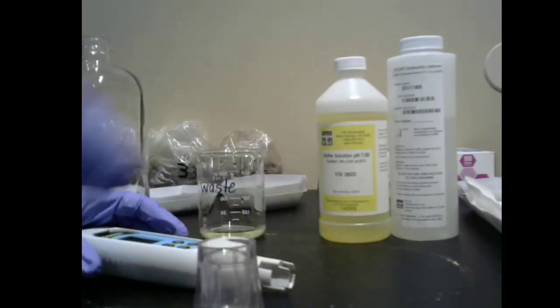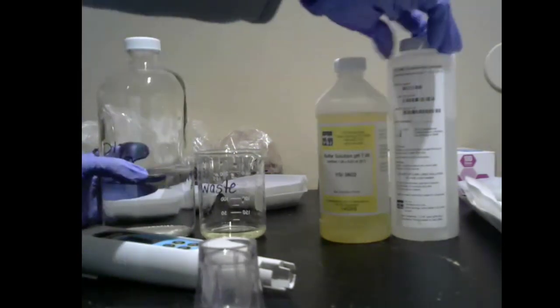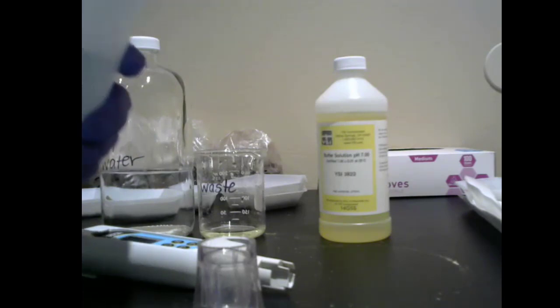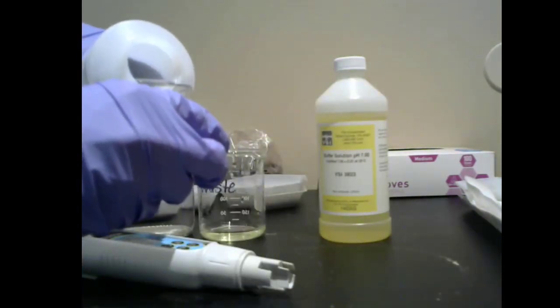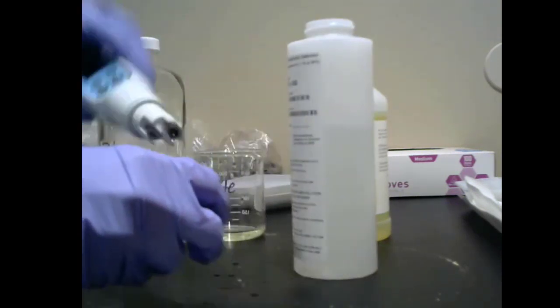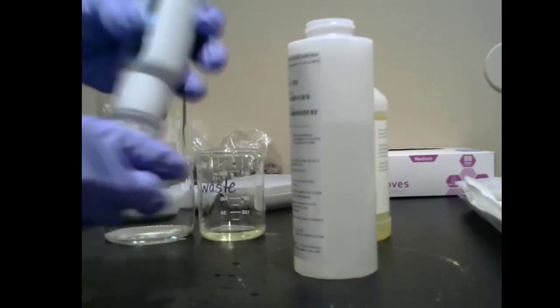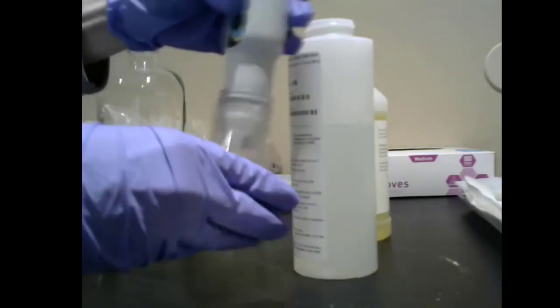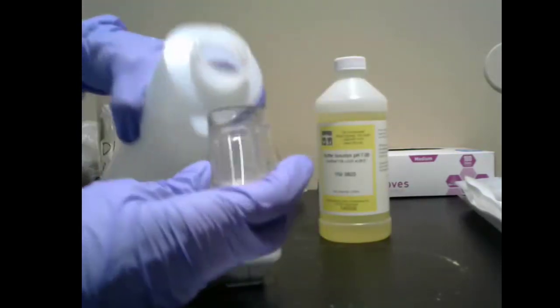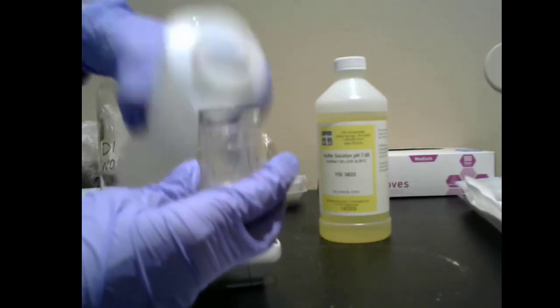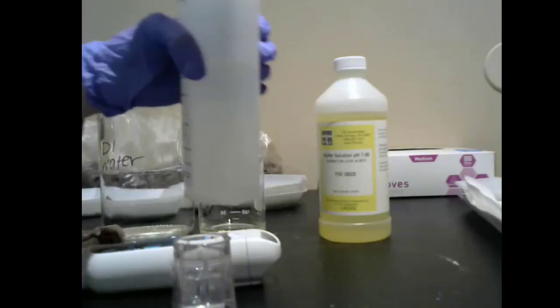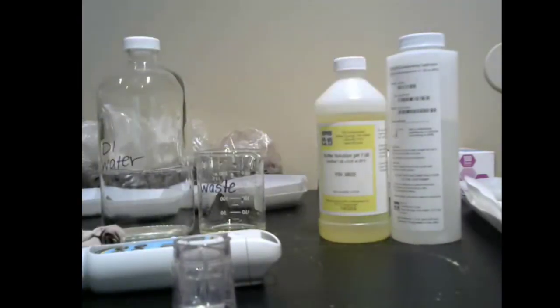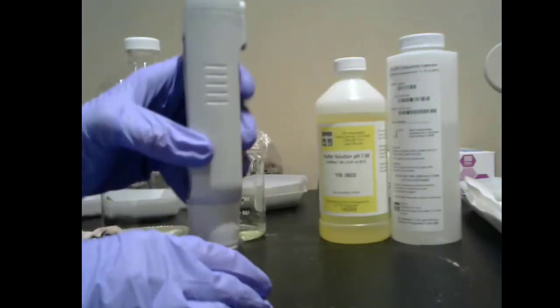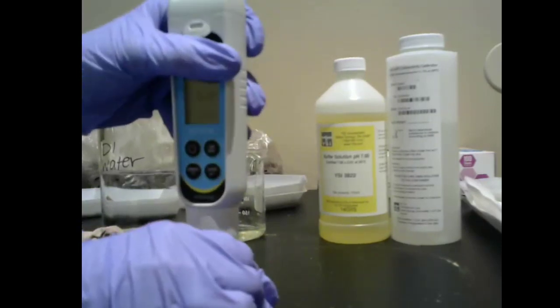So now let's move on to electrical conductivity, EC. Again, this is 1000 microsiemens per centimeter standard. And I'm just going to give this a little rinse, just like we did with the pH. Now I know everything is clean and ready to go for our conductivity spot check. So I'm going to again fill it to the fill line, so that my conductivity cell becomes completely immersed. Good, so my conductivity cell is completely immersed.